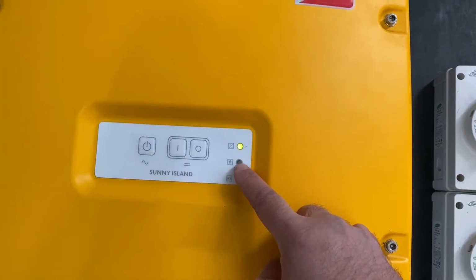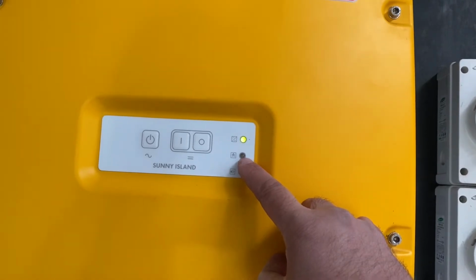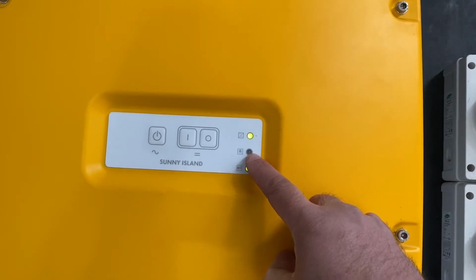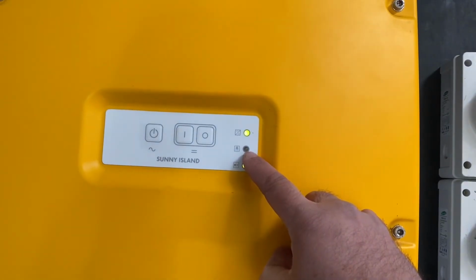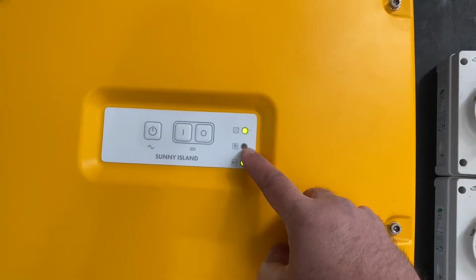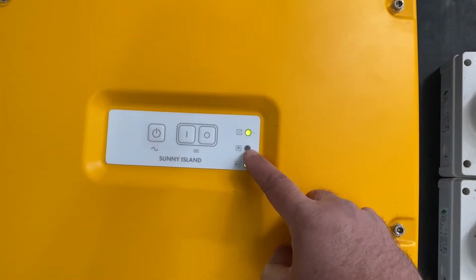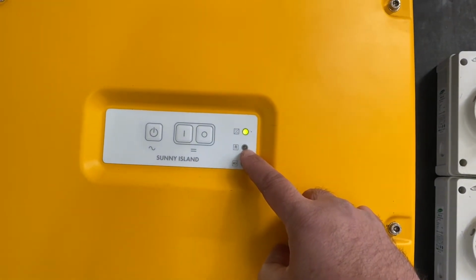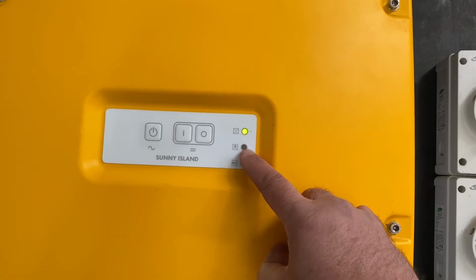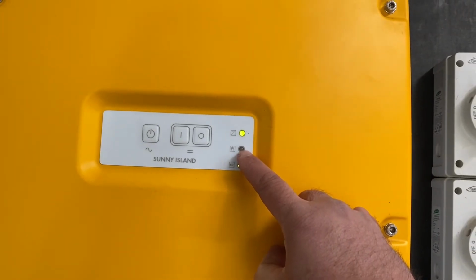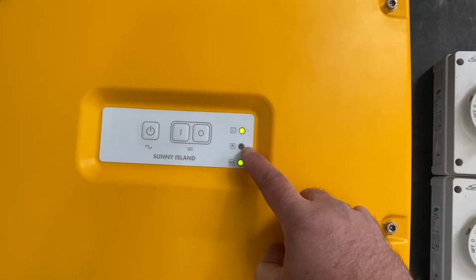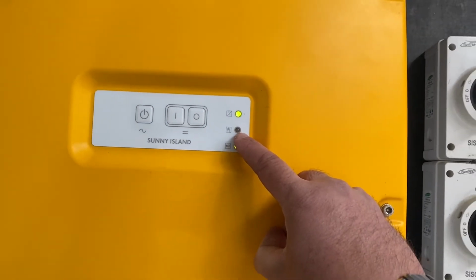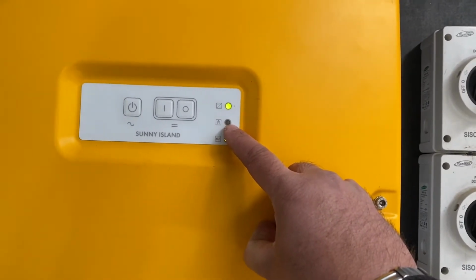Over here represents the generator supply. At the moment, the generator supply is off. If the generator starts, this will turn amber. When a generator is synchronized and delivering power, this will turn green. If it is red, then the generator is on, but the supply frequency is too high or low, or the supply voltage is too high or low. And in that case, it may flick to green and back to red, and flick to green and back to red. So when the generator is on, it will turn amber, and when it's delivering power to the site or batteries, it will be green.